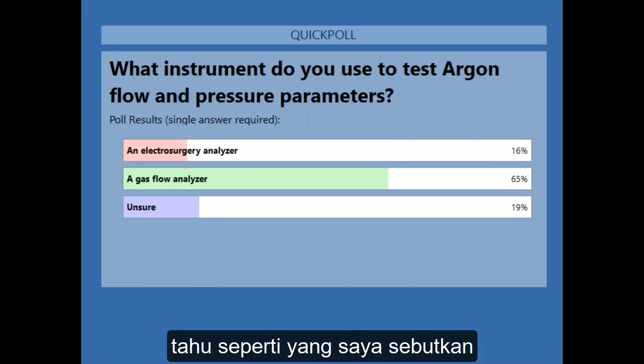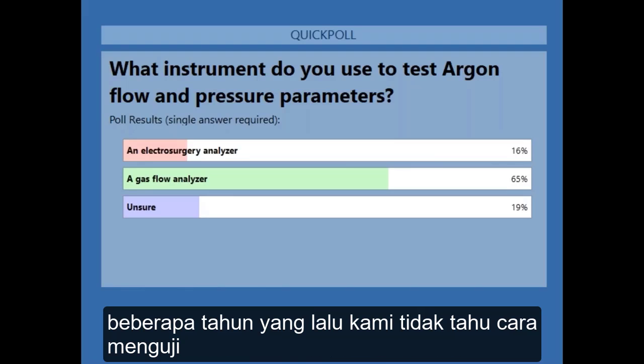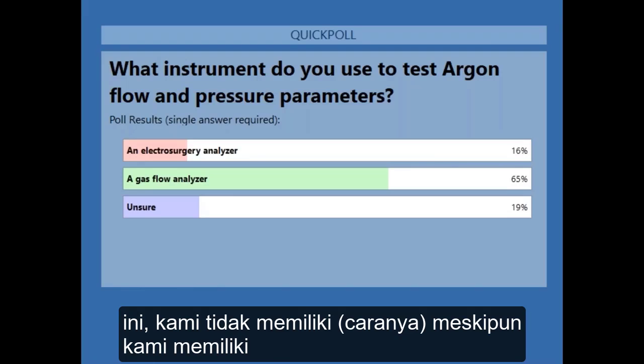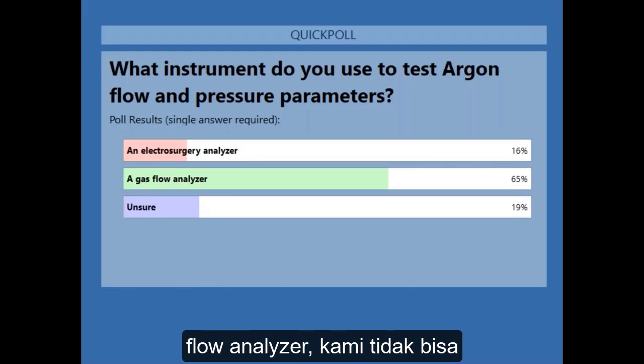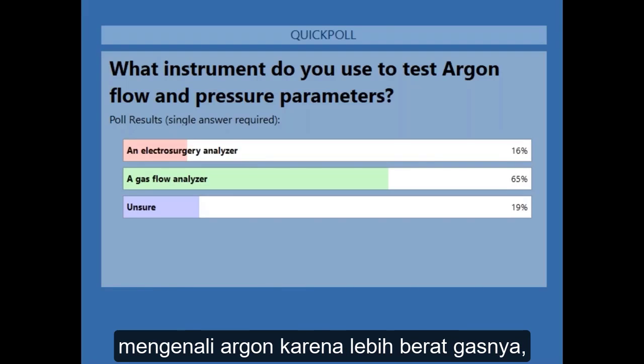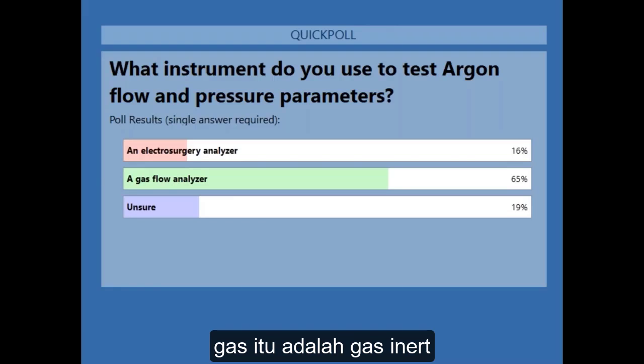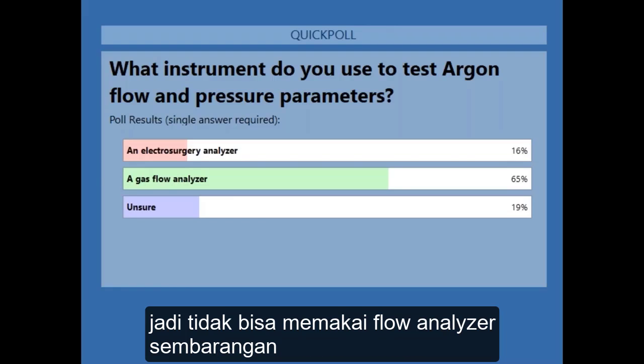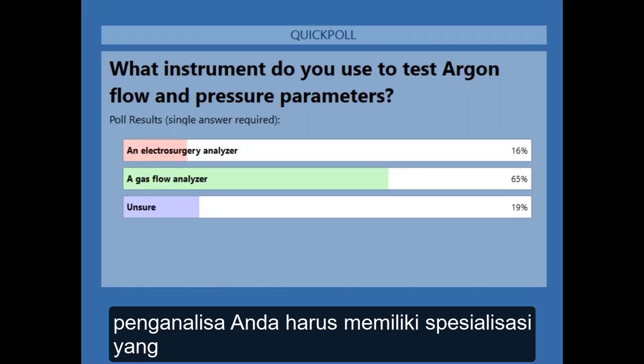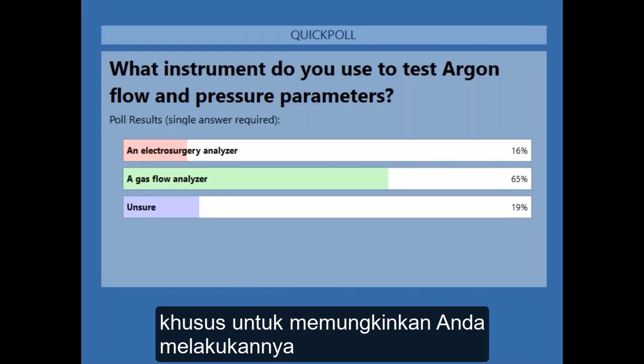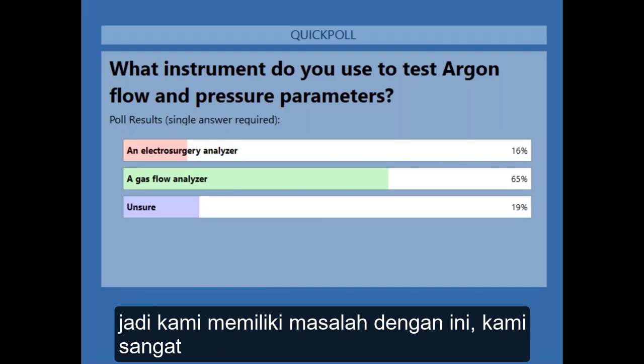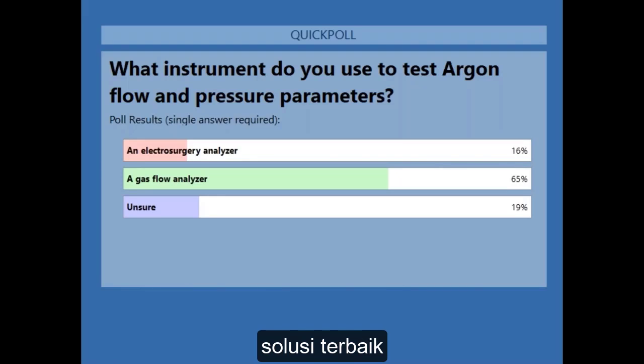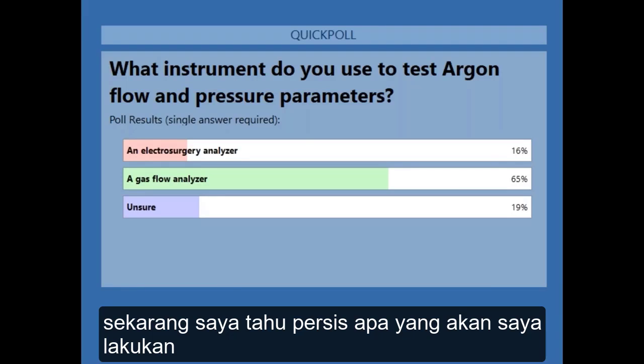Like I mentioned, a few years ago we didn't know how to test this. Even though we had a flow analyzer, it wouldn't recognize argon because it's a heavier gas. It's an inert gas. So it doesn't just take any flow analyzer. You have to have a pretty specialized flow analyzer to do it. So we had problems with this. We were very unsure and trying to come up with the best solution. Yep. But now I know exactly what I'll do.